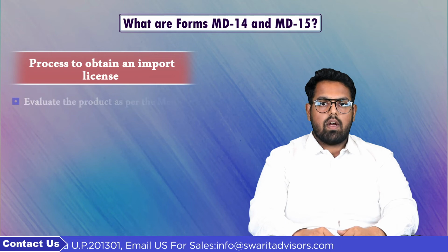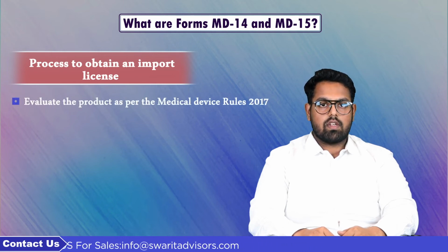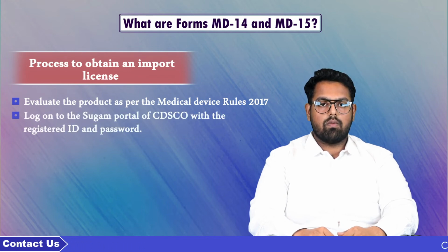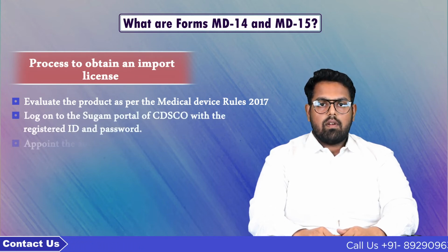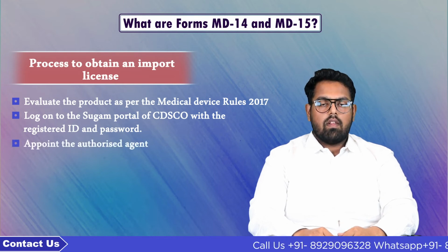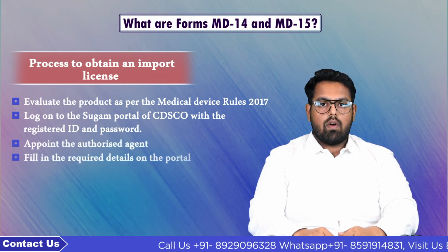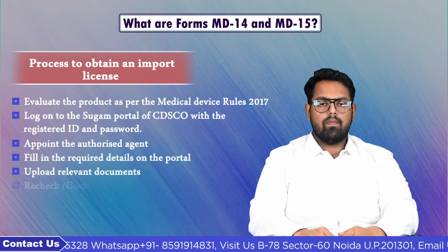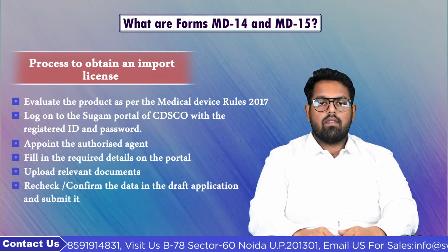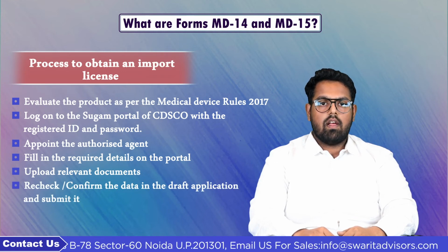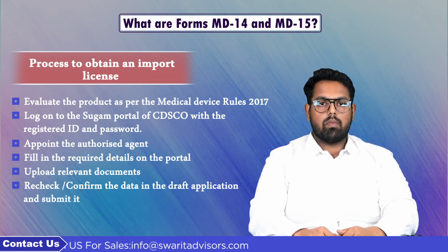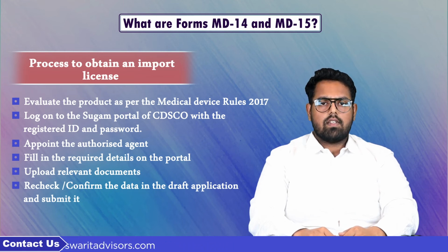The process to obtain an import license as per Form MD-15 is fairly simple. First, the applicant must evaluate that the product is as per the medical device rules standards. Next, the applicant must log on to the Sugam portal of CDSCO with registered ID and password. The applicant must appoint an authorized Indian agent. Then the applicant needs to fill in the required details on the portal and upload the relevant documents as mentioned before in the video. Lastly, the applicant needs to recheck and confirm the data in the draft application and submit it. CDSCO may ask the applicant some queries. These queries need to be addressed immediately. Once the authorities are satisfied, the medical device import license shall be granted to the applicant.